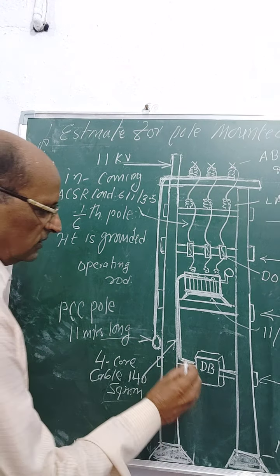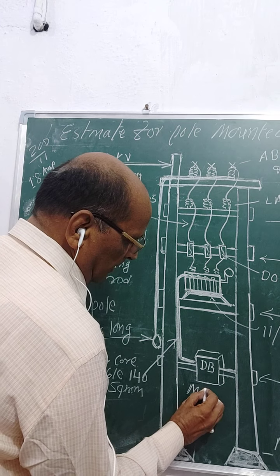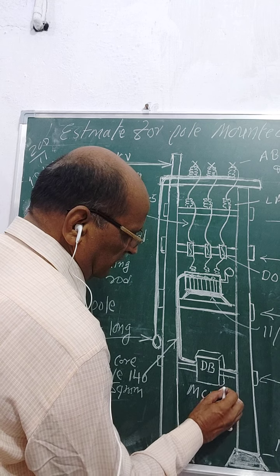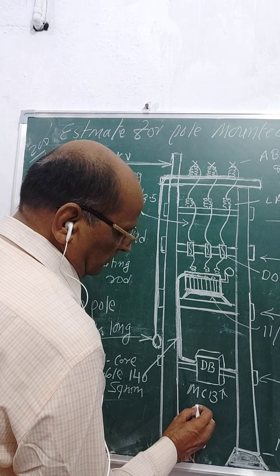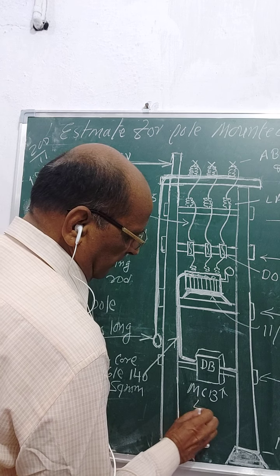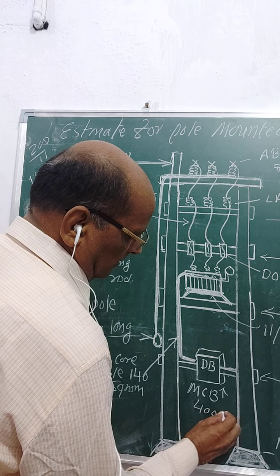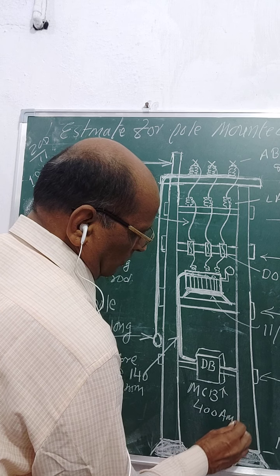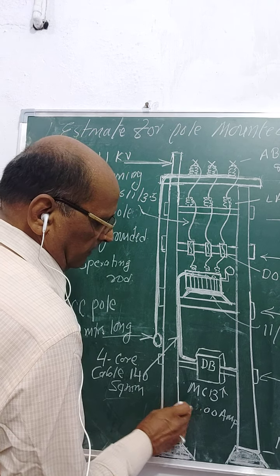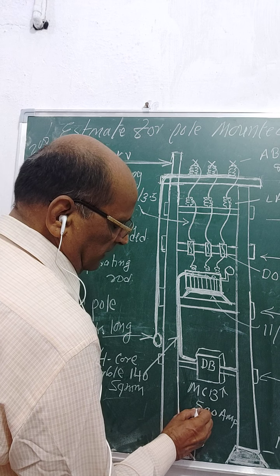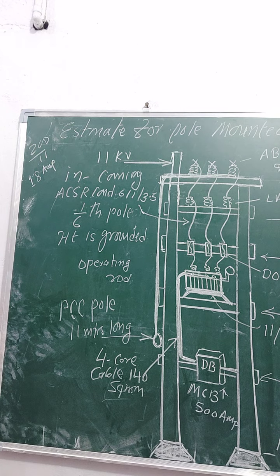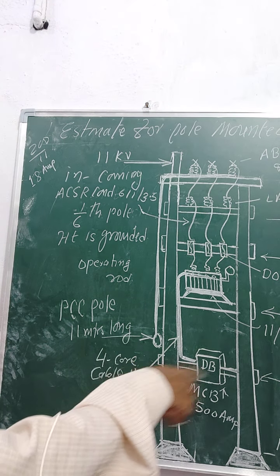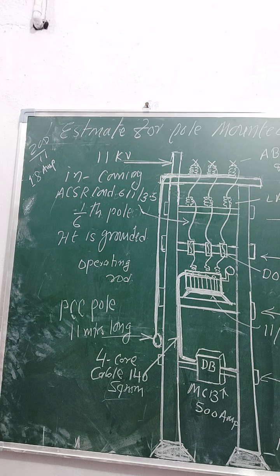In the distribution box there is MCB and bus bar in this; for a rating of about 200 kVA it is about 500 ampere MCB, because 200 kVA divided by, 200 kVA transformer divided by 0.4 kV, so it will come about 500 ampere. So MCB of 500 ampere with bus bar is mounted inside this. From this, a line is taken to supply the LT line for distribution.